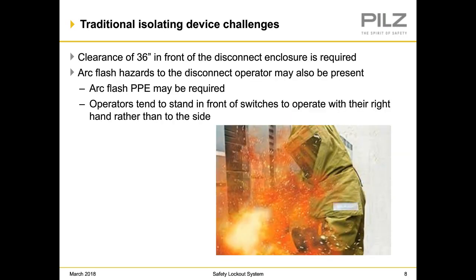Clearance of 36 inches in front of the disconnect enclosure is required. Arc flash hazards to the disconnect operator may also be present, and arc flash PPE is required. And operators tend to stand in front of the switches and operate with the right hand. More people are right-handed than left-handed, and all the switches have the disconnect handle on the right-hand side.